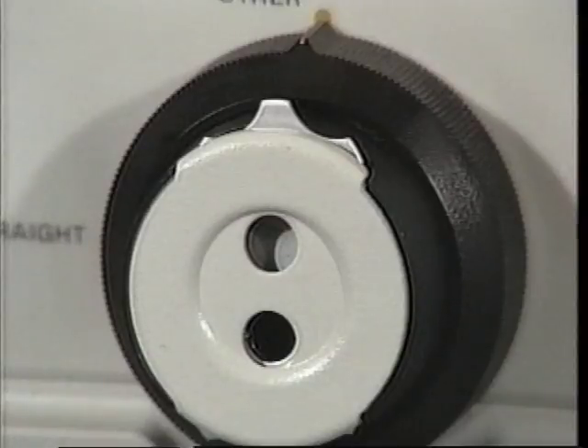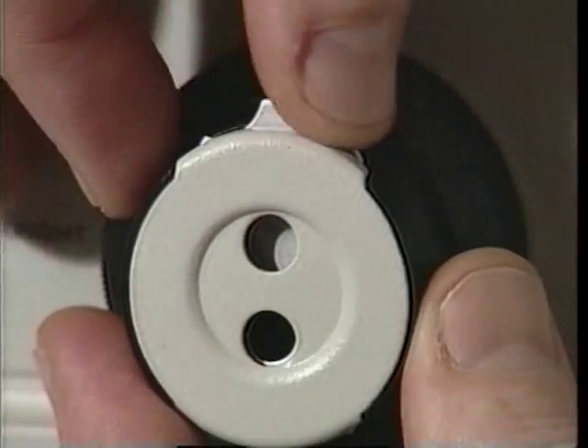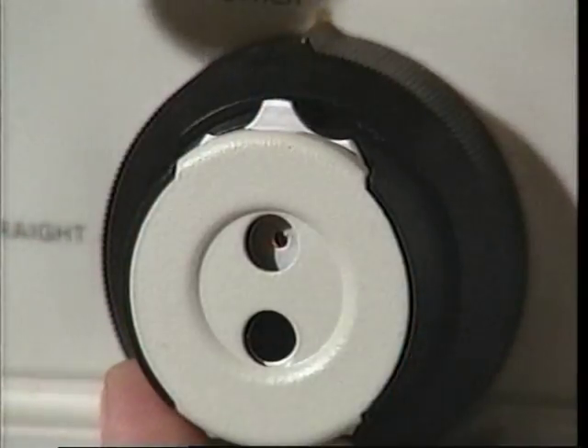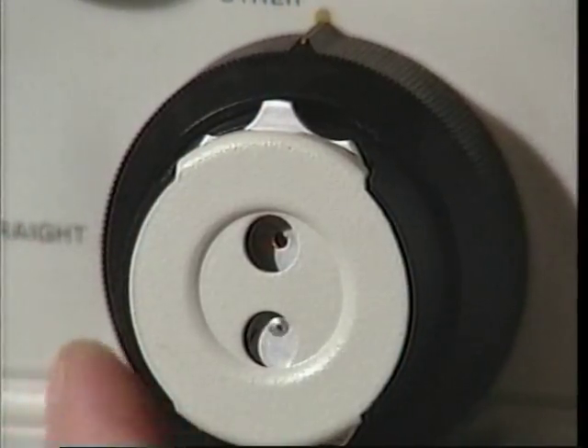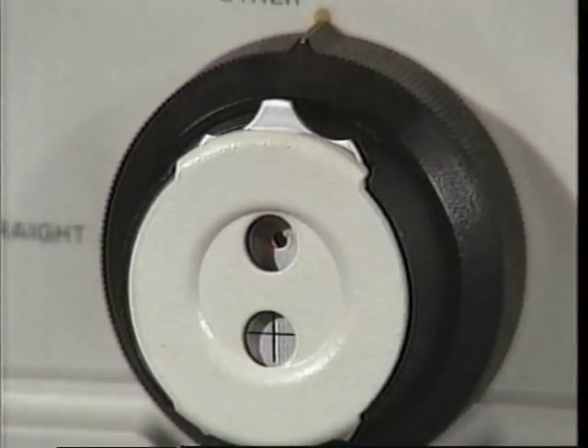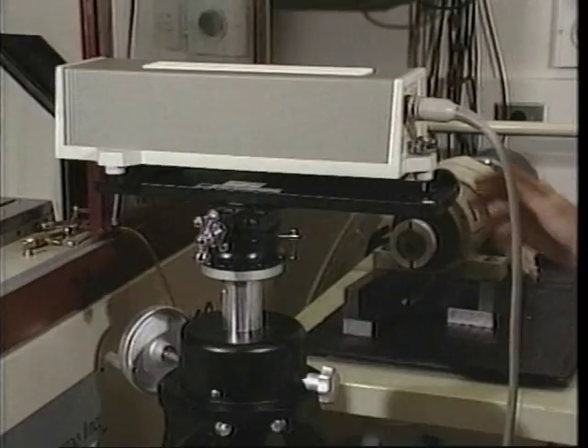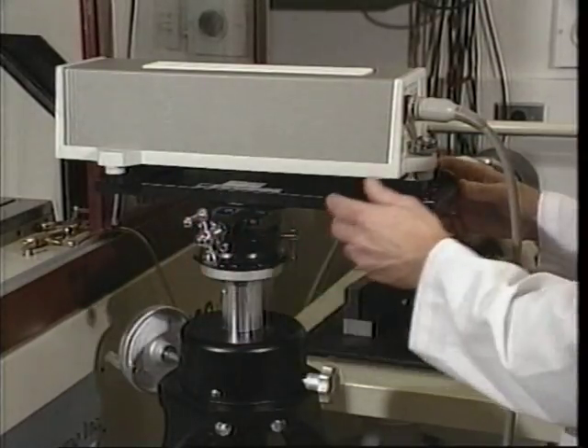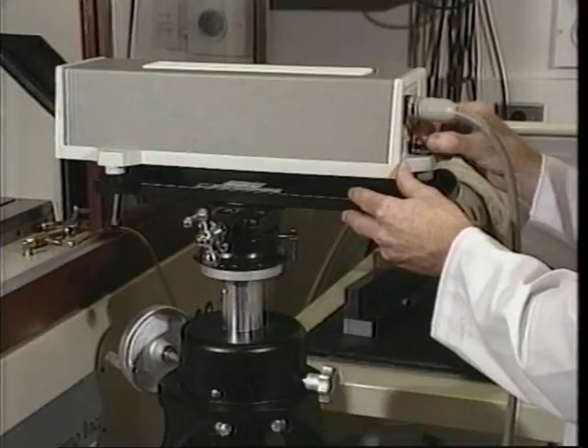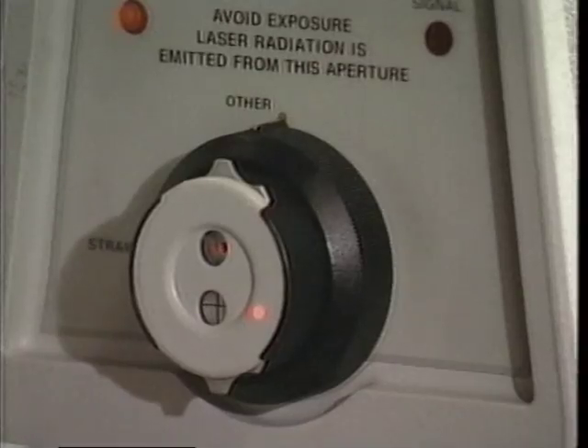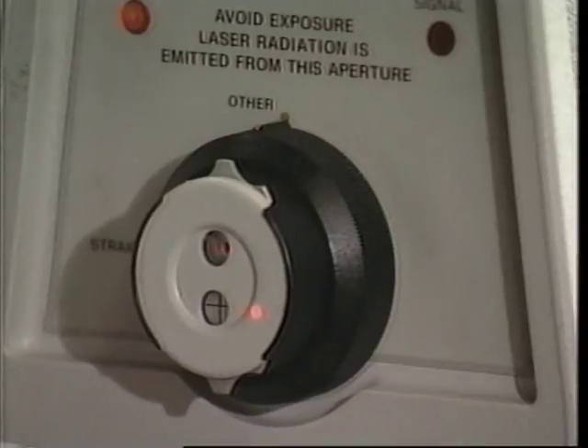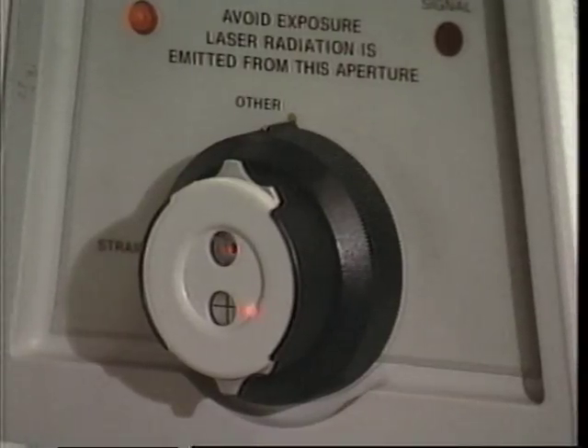The gun sight method will be used to precisely align the optics. Select the aperture control's smaller opening for the laser beam's exit port. Rotate the target over the return port. Using the translation and rotation adjustments on the tripod, position the laser head so that the interferometer assembly's returning beam falls on the target over the return port.